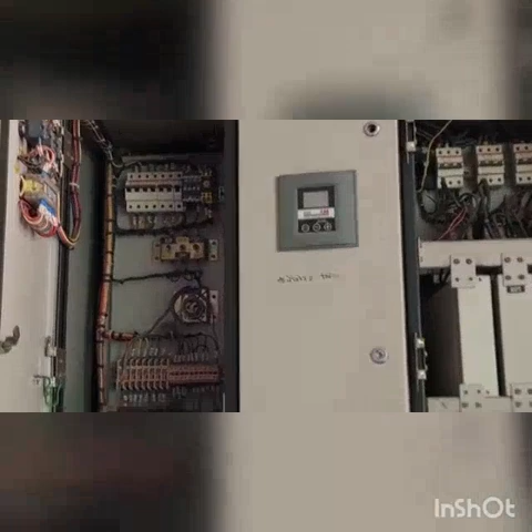As the system is a 3-phase 4-wire system, we have used a wiring adapter, and the voltage cord and clamp-on sensors are connected at the load side for voltage and current measurement. The Hioki PQ analyzer gives readings for voltage and current for each phase and their THD percentage. It also provides power factor and many other details. It also gives the harmonic values up to the 50th order.